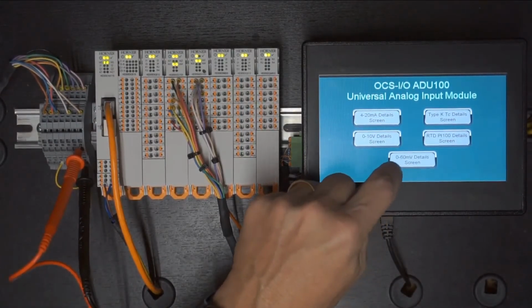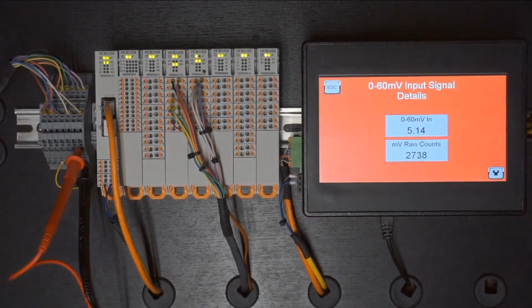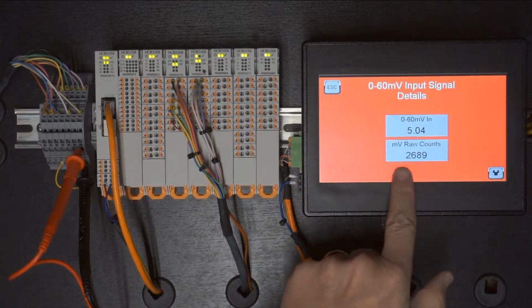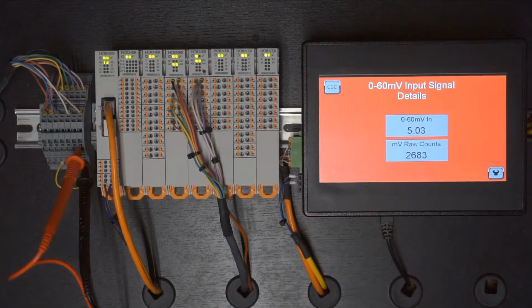And let's take a look at 0 to 60 millivolts. Okay, so again, we are sneaking in on 5 millivolts, and you can see our raw counts there. Now we're scaled 0 to 32,000 correlates 0 to 60 millivolts. So you can see I'm right about 5 millivolts. Let's go ahead and bump that up to 20 millivolts. We should see our reading respond, and it is. And again, we can go all the way up to 60 millivolts with this particular range, but with most load cells, they're going to be in the 20 millivolt or 30 millivolt range most of the time. So there's our millivolt range.